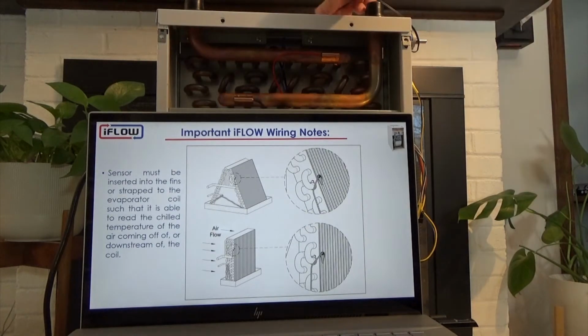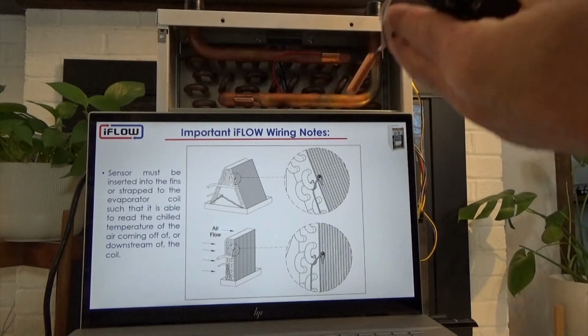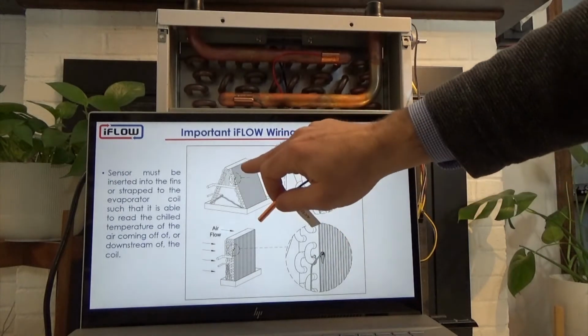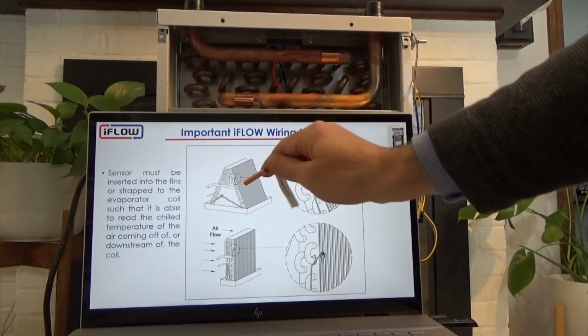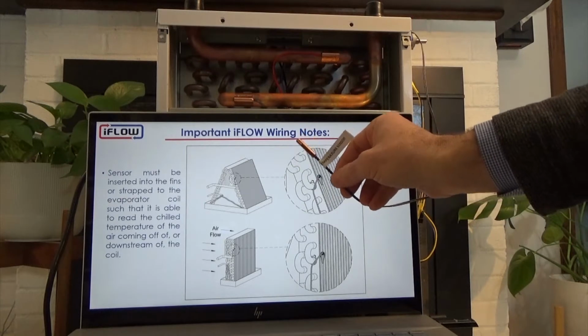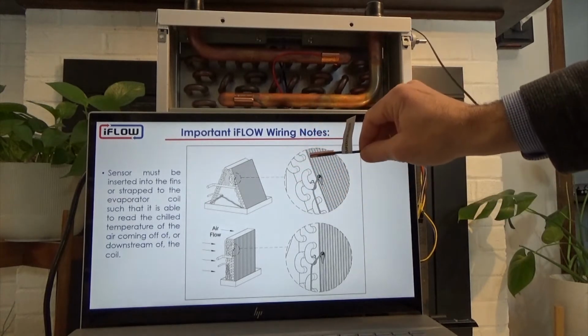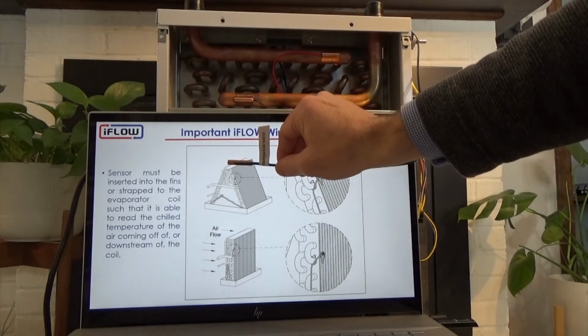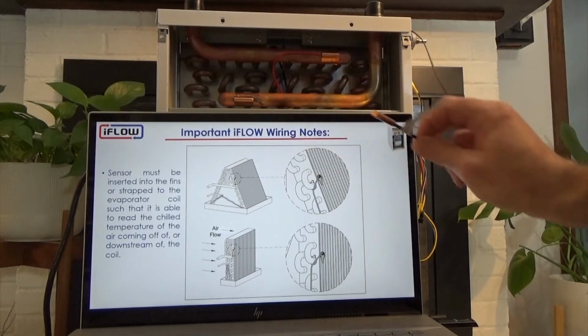So when you have this sensor, you can insert it into the fins of the AC coil, or you can strap it somehow to one of the elbows at the top. You just have to make sure it is actually reading the air temperature coming off the top of the coil.